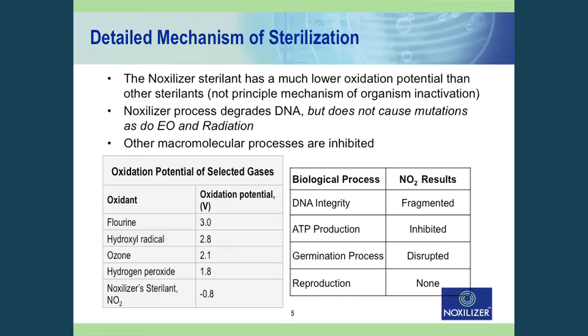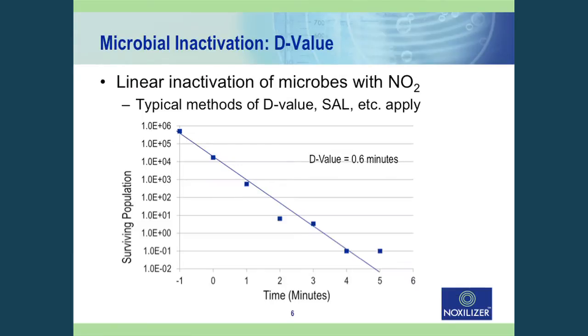With every sterilization process, you have to show the inactivation curve or D-value curve. For conditions of 5 milligrams per liter NO2 concentration in the chamber, we had a D-value of about 0.6 minutes and a linear 6-log reduction of the spore population over the full exposure time shown.